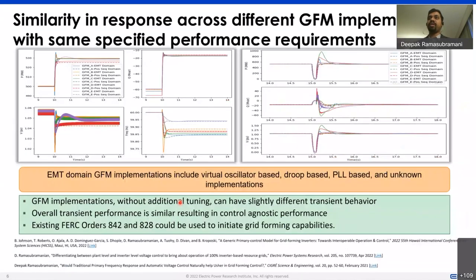And if we take that specification, that baseline about performance from the perspective of fast voltage control, and then compare it against different grid forming inverter implementations, here we have compared 5 different grid forming inverter implementations, going from virtual oscillator, droop-based, PLL-based, and even a couple of them that we intentionally didn't look under the hood of, because we just wanted to see, supposing I am a system planner and I don't know what is inside, what is the performance that is provided by that unknown grid forming inverter implementation? And we see that even in the basic sense, without additional fine tuning, with only a very coarse level of tuning, there is a similarity in the transient performance across these 5 different types of grid forming characteristics.